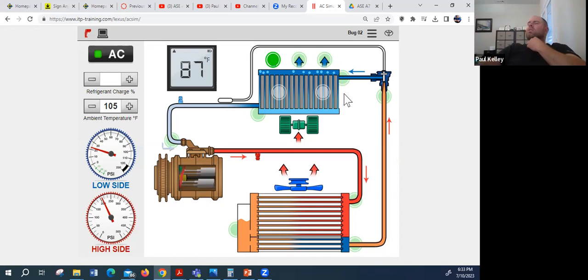I mentioned this a couple times, it's possible that an evaporator could cool more in the beginning and less in the end, and you can see it's picking up 11 degrees from beginning to end. So if we look at this, we got 27 coming in, 54 here, it's already up to 64 by the end of that evaporator internal temperature. So by the time it leaves, 76 - I mean there is something wrong there, that's not good.